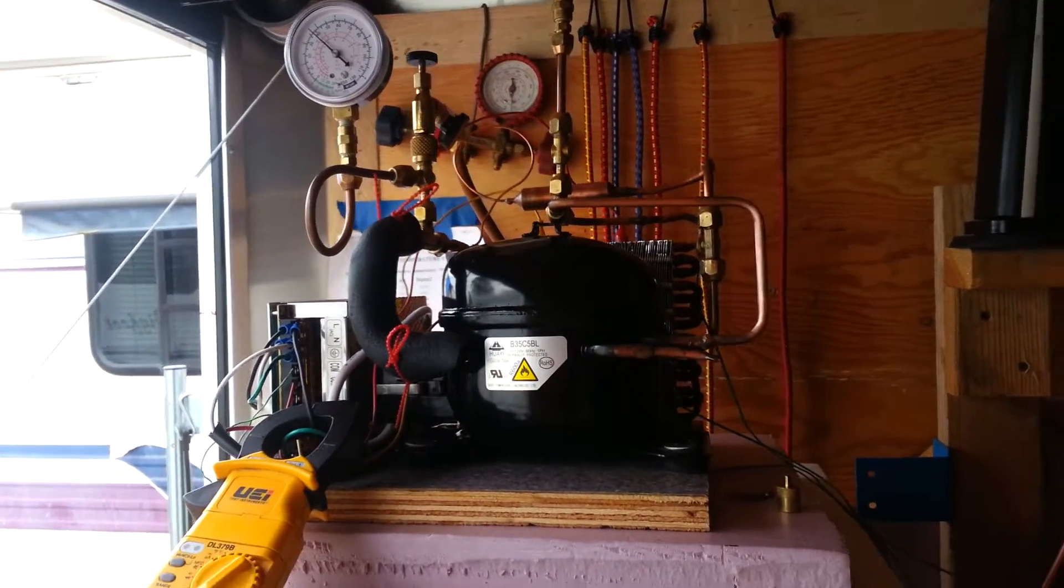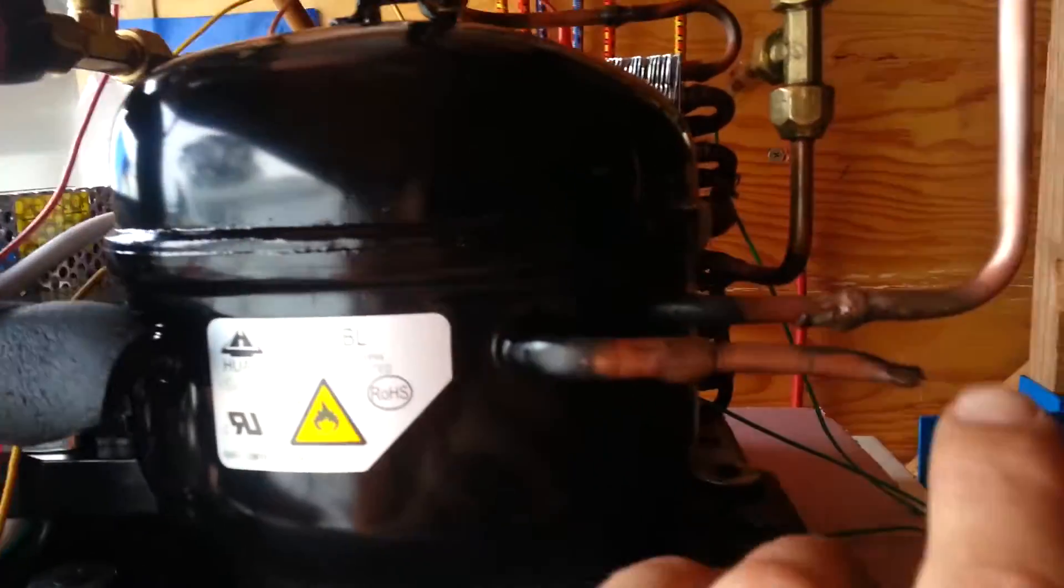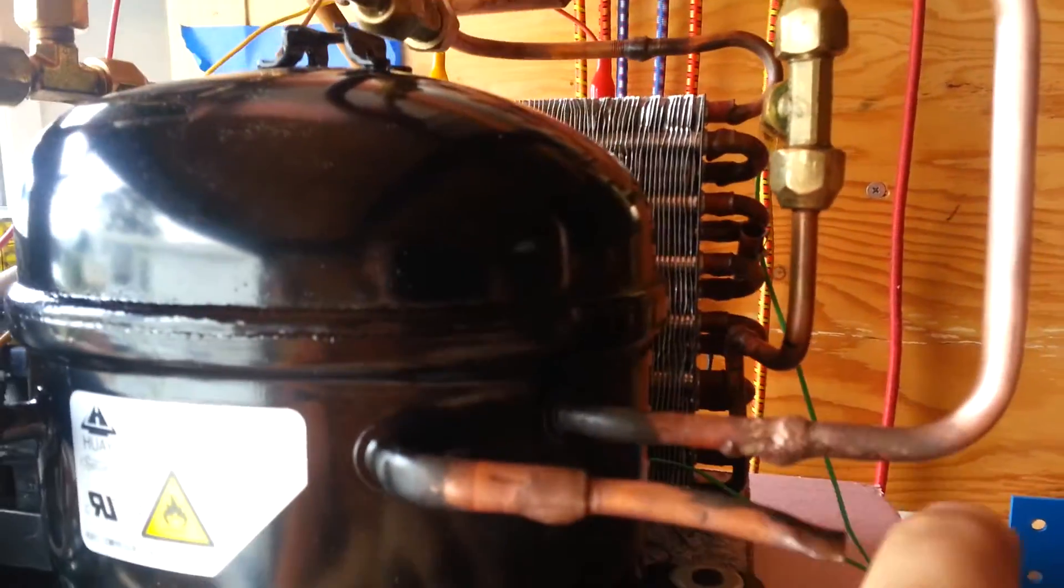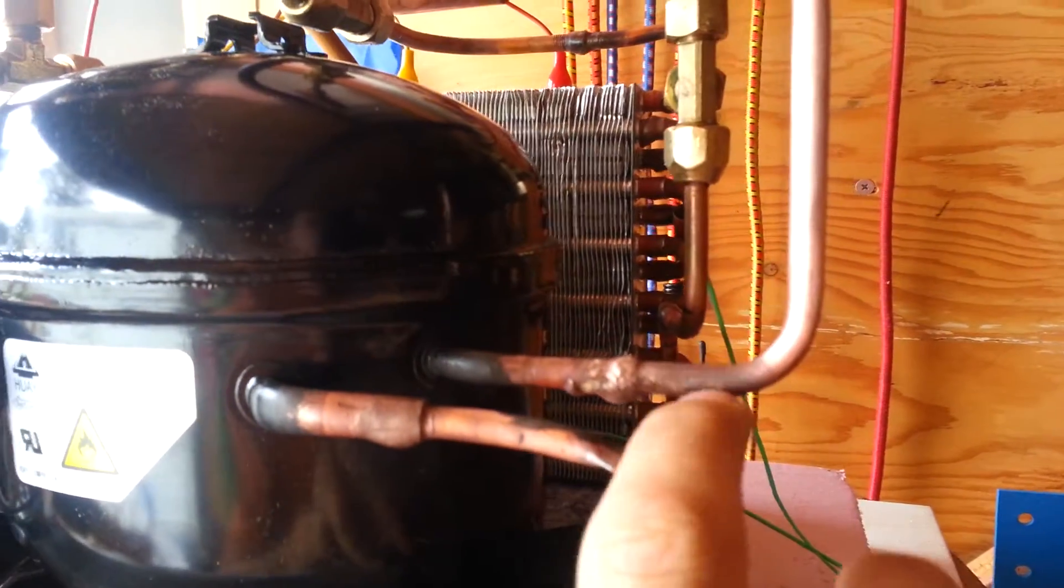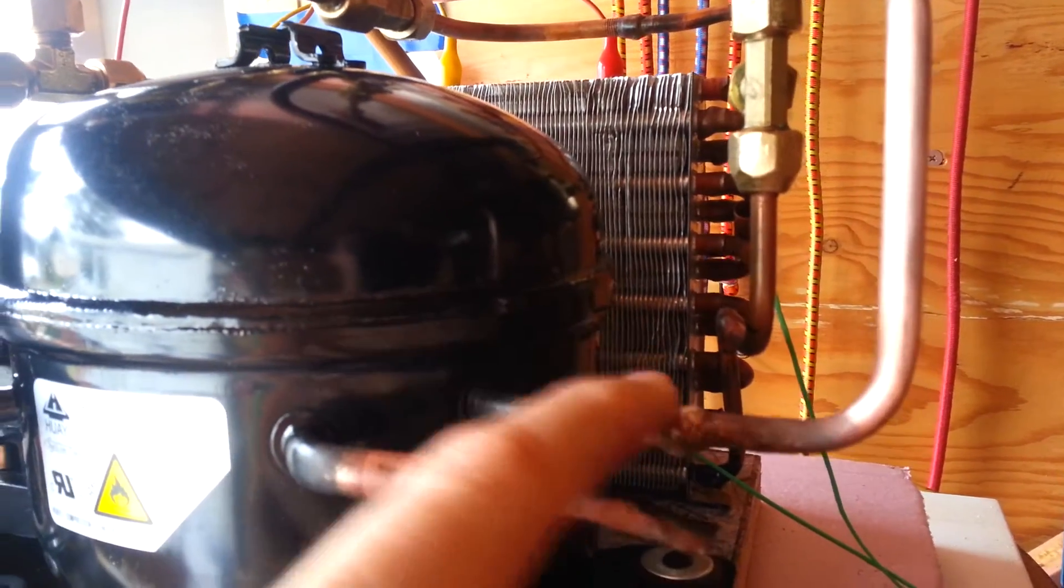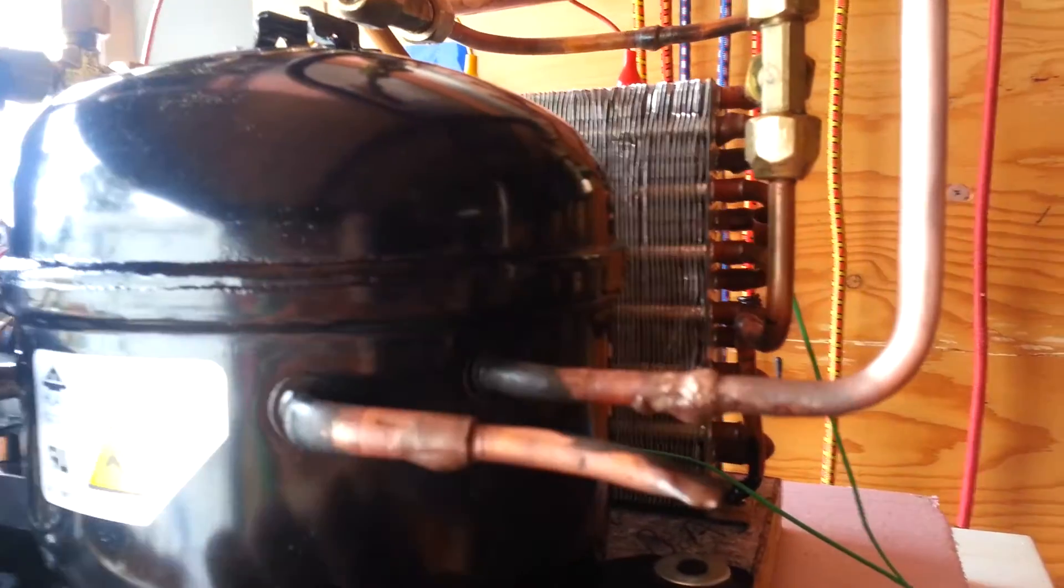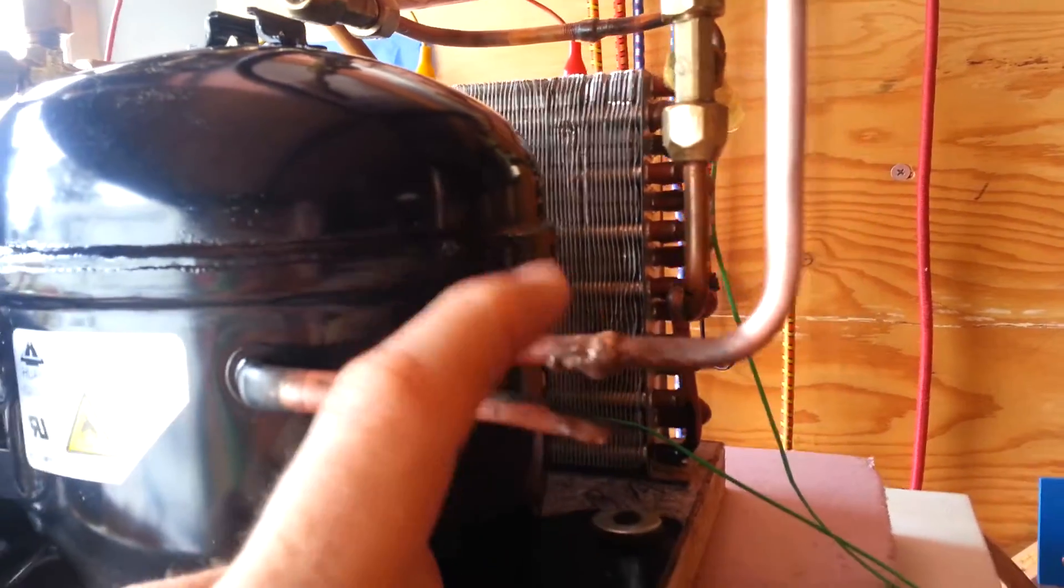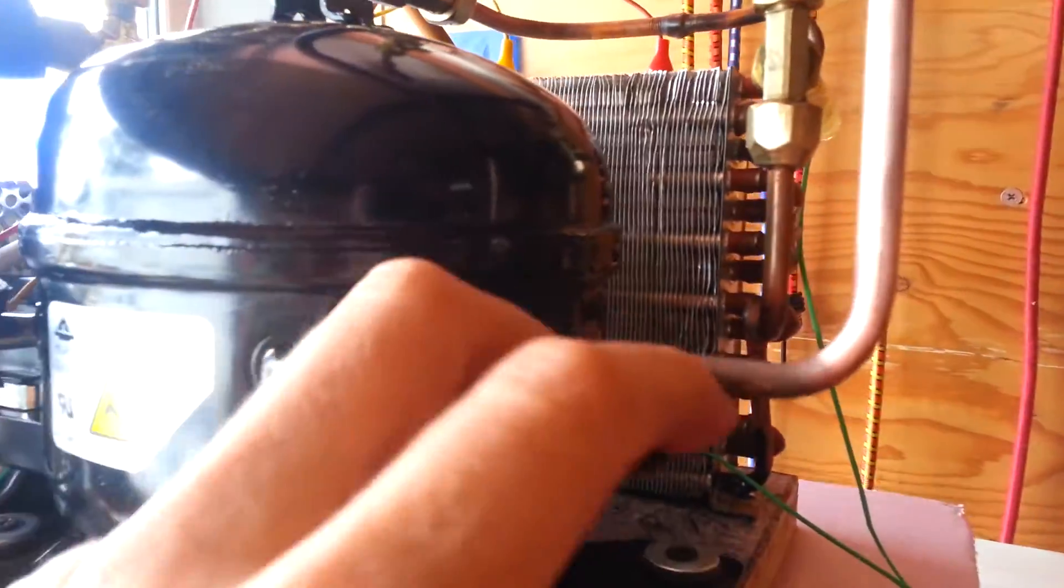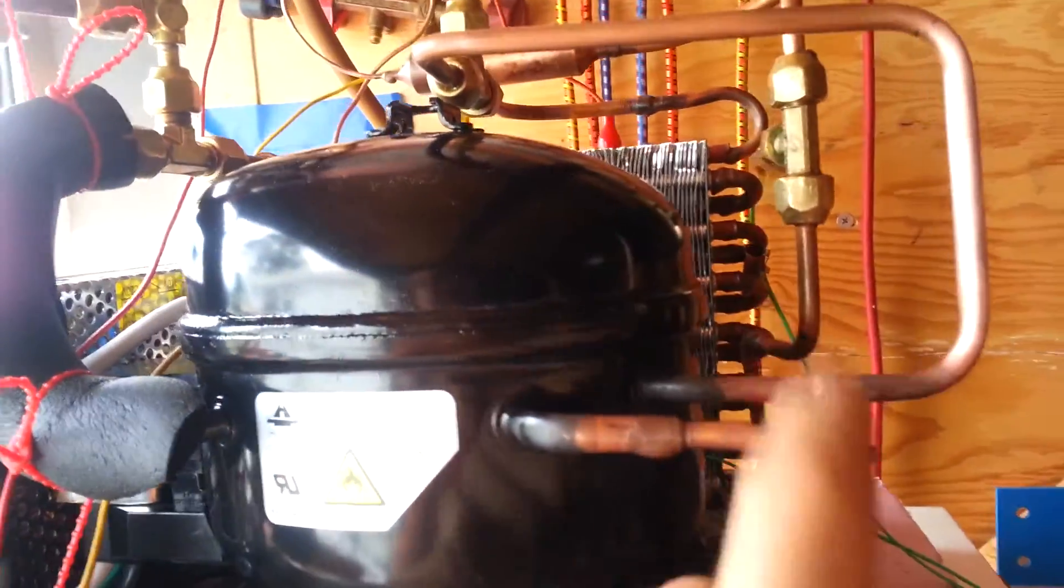It took me about an hour and a half to swap out the compressor. Of course, I had to remove the original fittings. Now my brazing here is really ugly. I'm actually kind of ashamed of it. I was running short on propane, my fuel I used to braze with, so I wasn't able to get the heat and it ended up pretty ugly. So I found a bottle of MAPP gas and switched over to that and was able to clean it up a little bit.